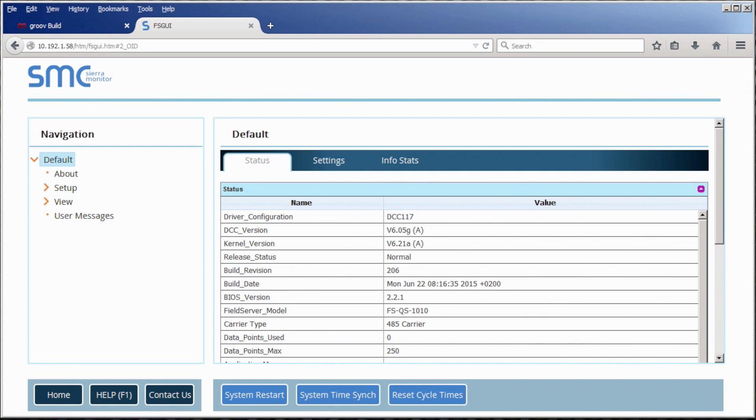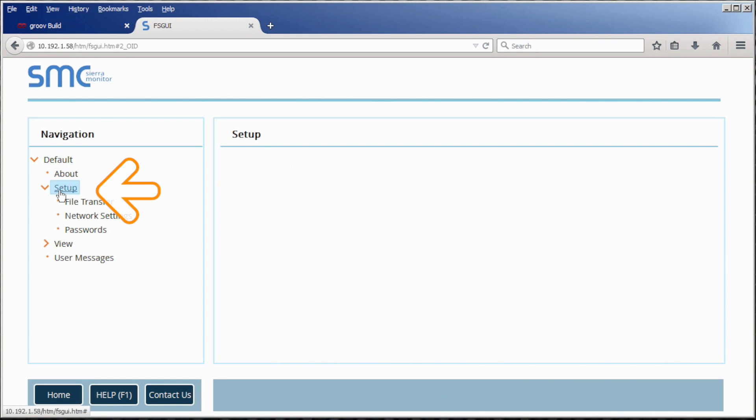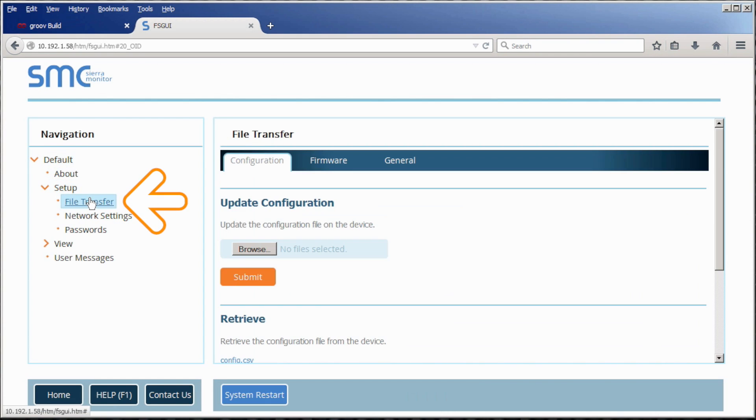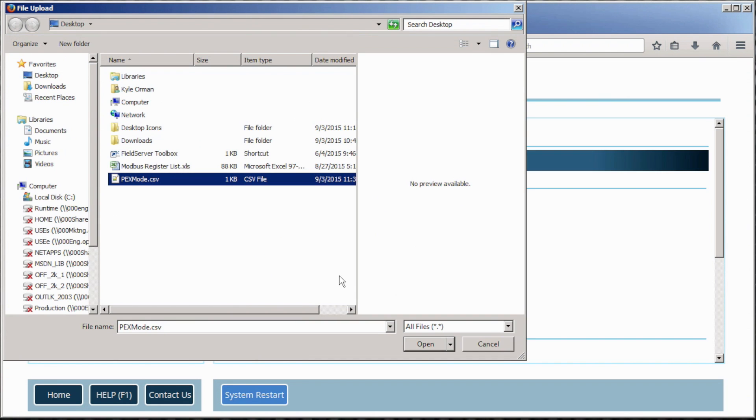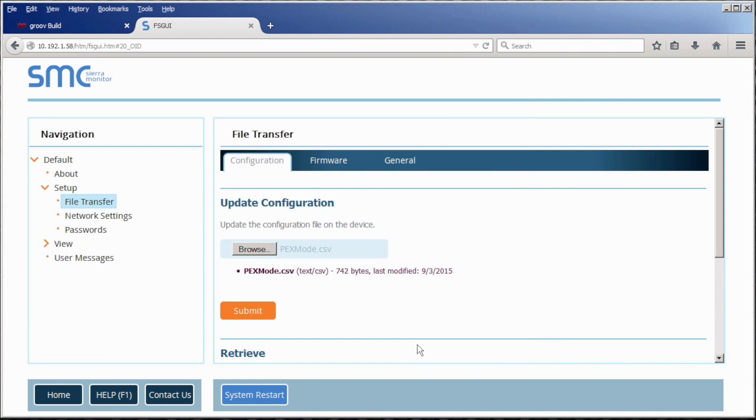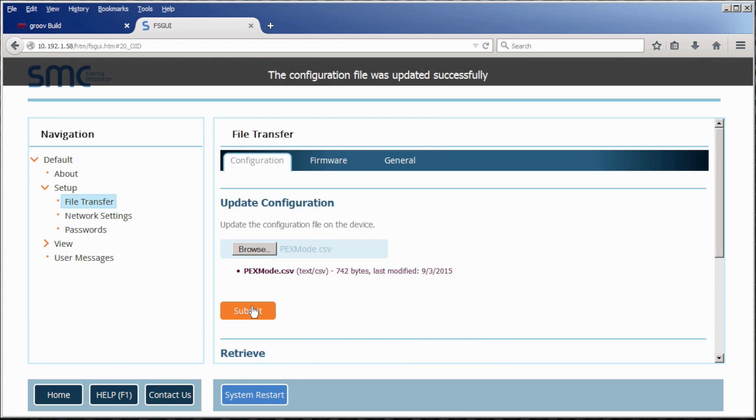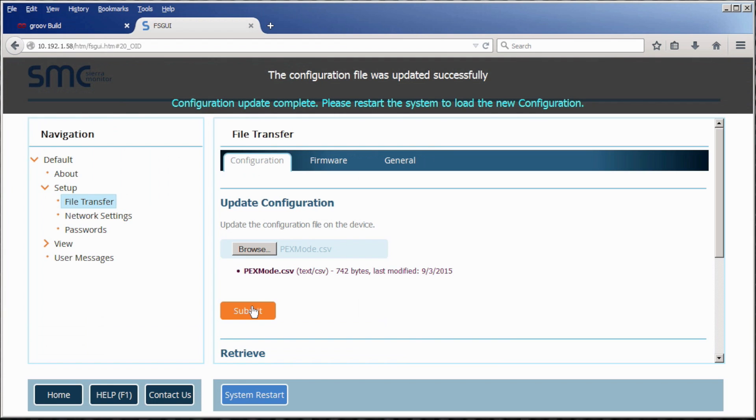We want to load the configuration file, PEX mode.csv, the same one we just edited, onto the QuickServer. To do this, on the left hand side, click the drop down and choose setup. Here we will click on file transfer and browse for the PEX mode file. Choose PEX mode.csv, click open and then submit. This saves the file.